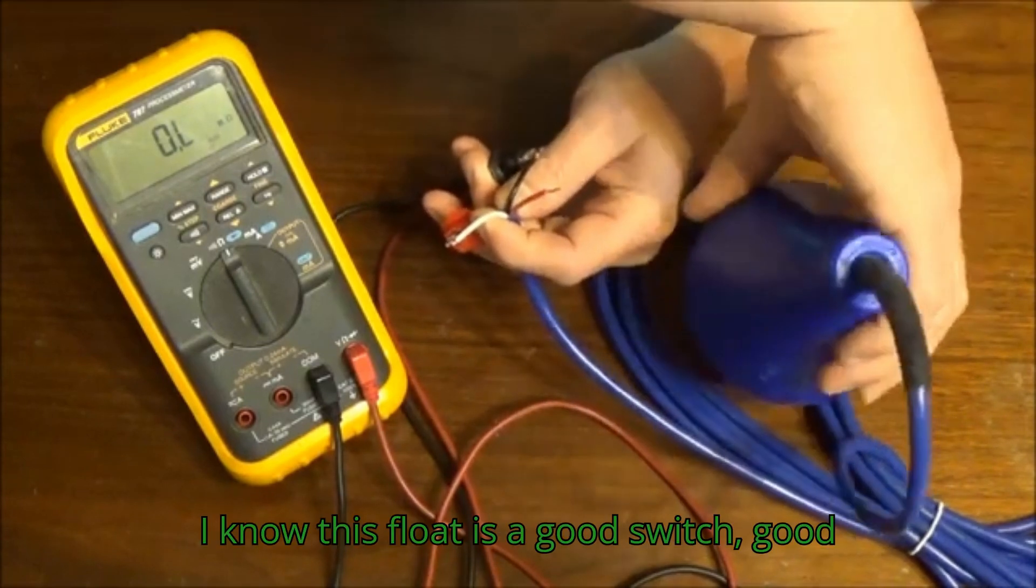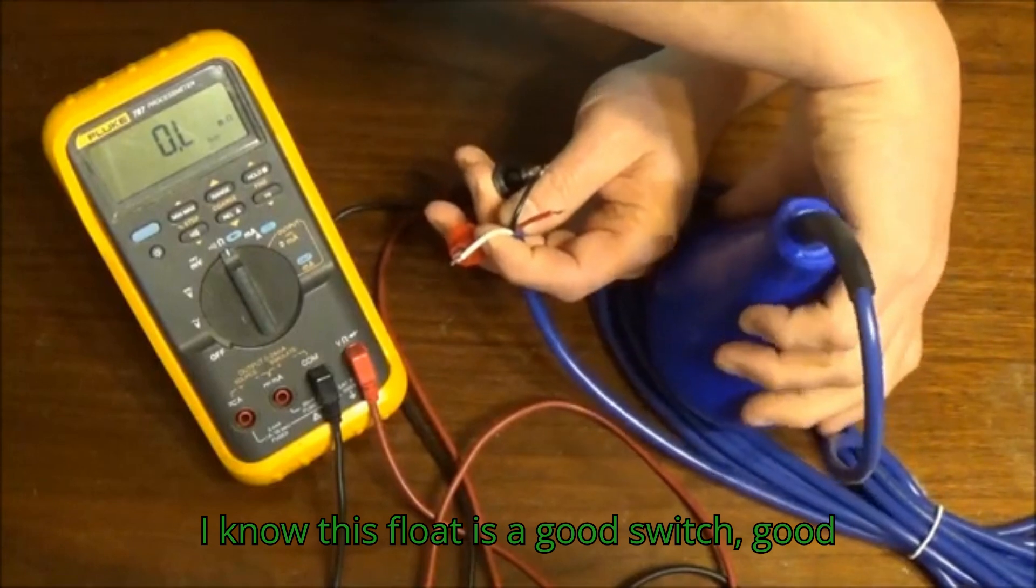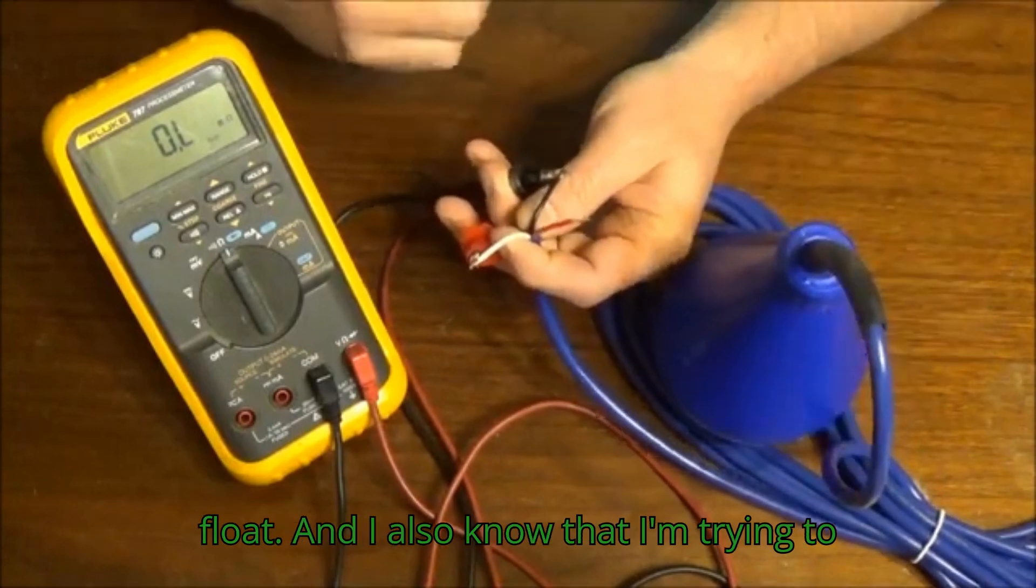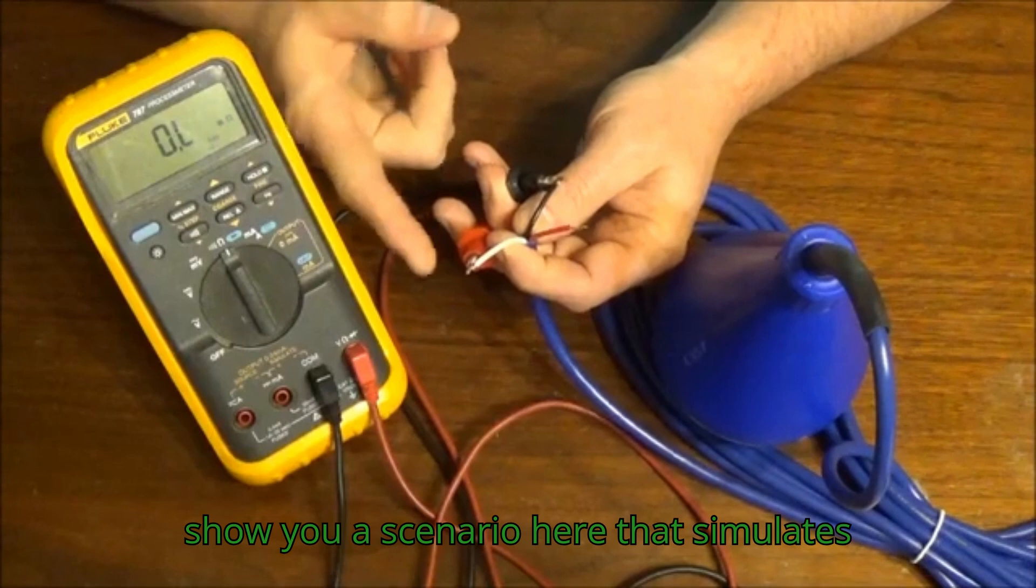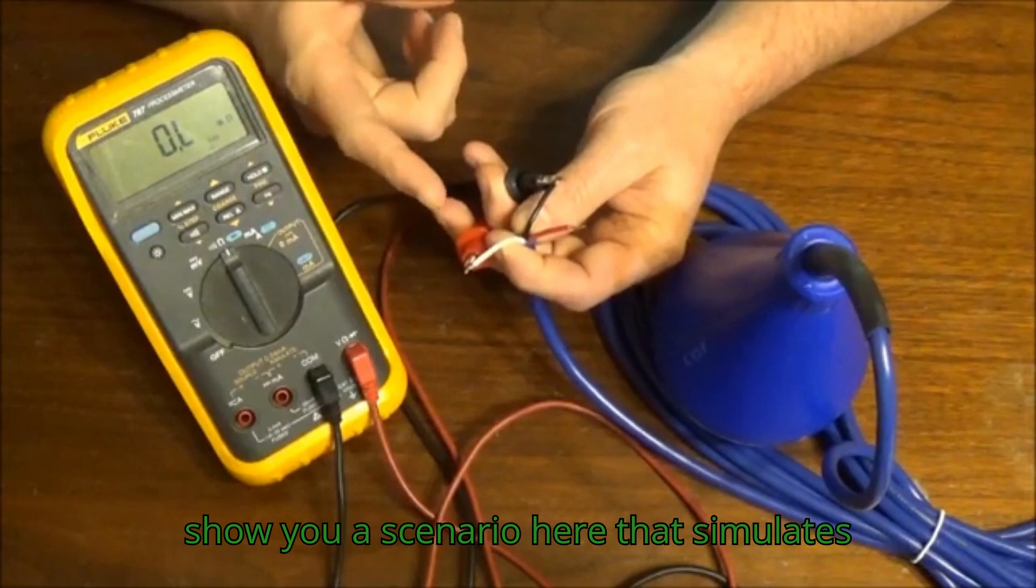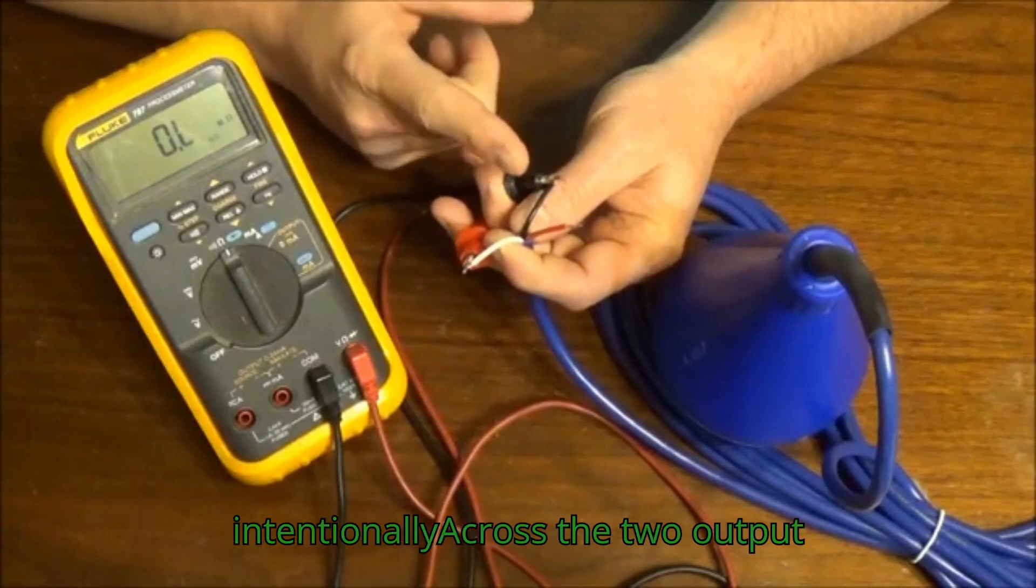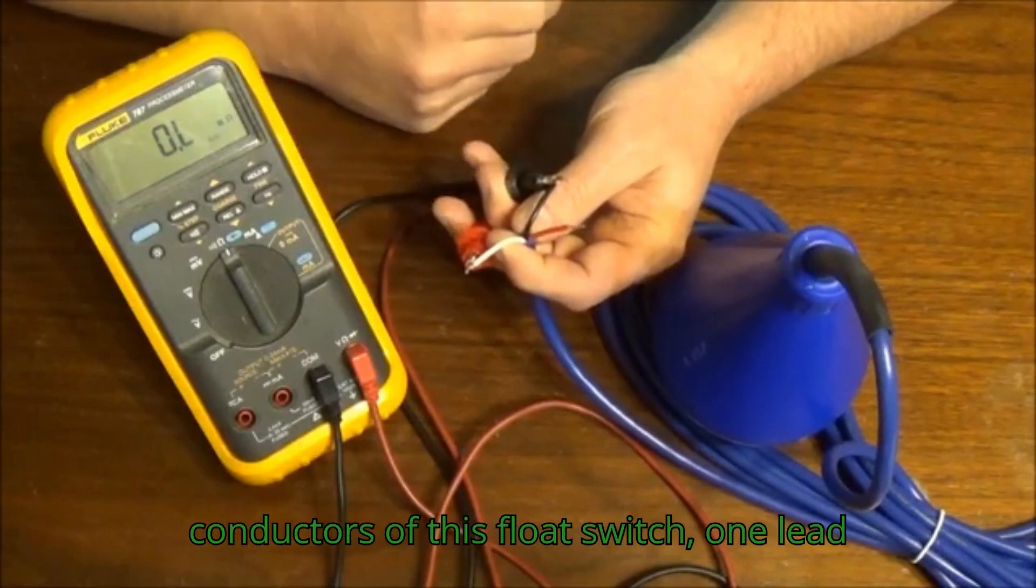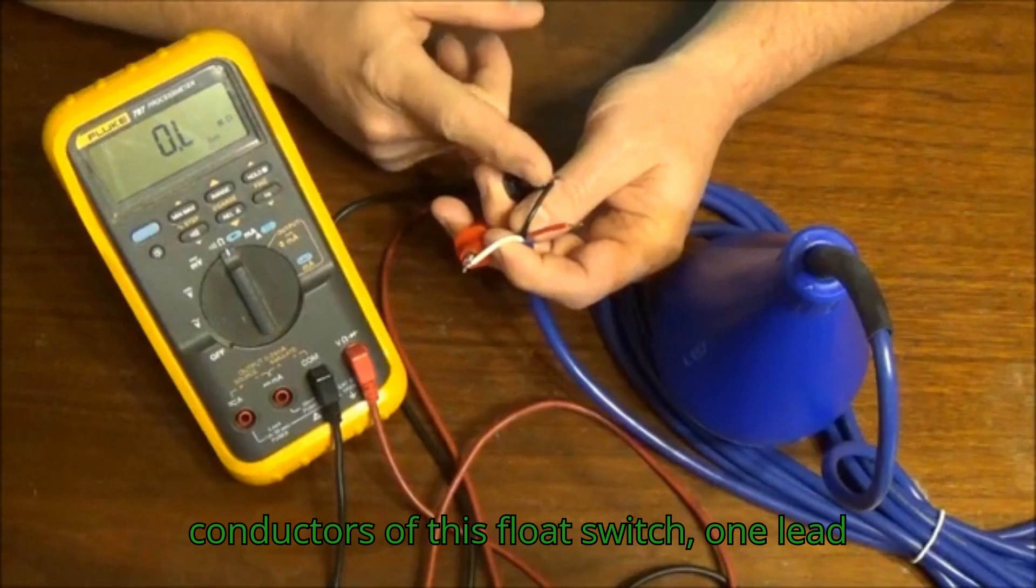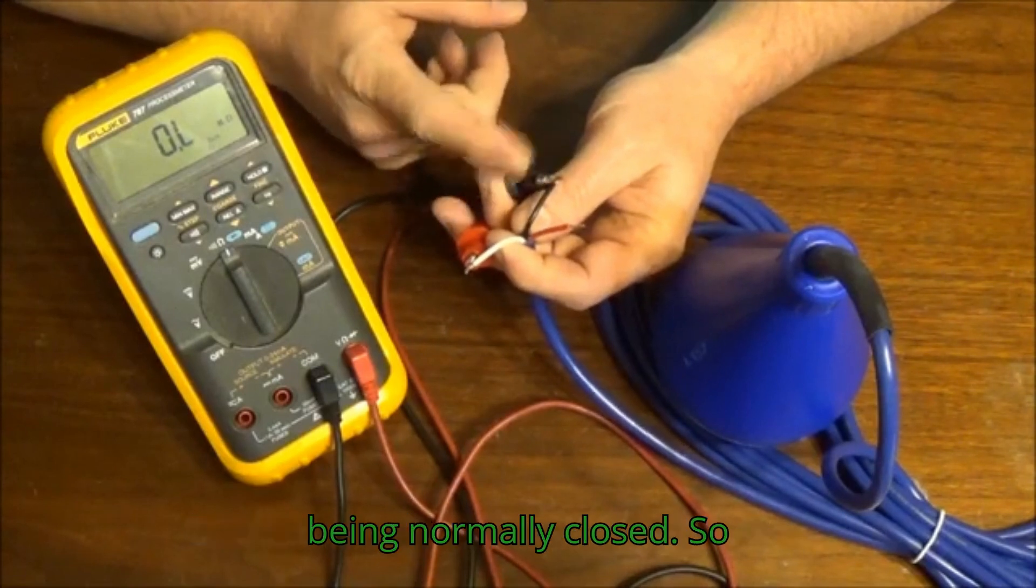But I know this float is a good switch, a good float, and I also know that I'm trying to show you a scenario here that simulates a bad float. I measured intentionally across the two output conductors of this float switch. One lead being normally open and the other lead being normally closed.